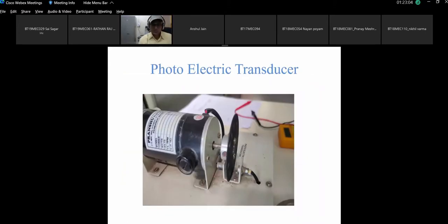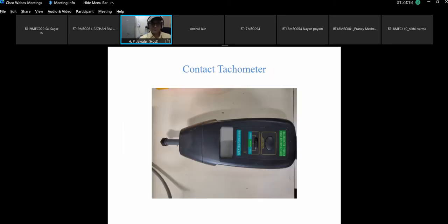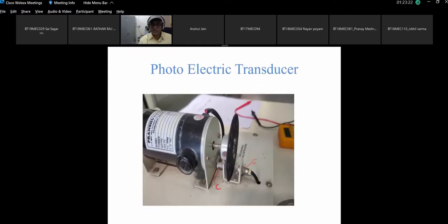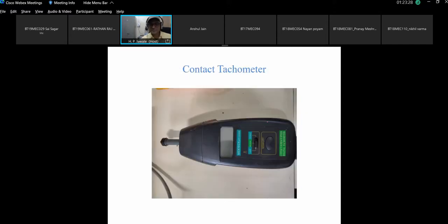So this is a motor. This is the emitter and this is the collector. These are the two elements: light emitting device and light collecting device, or signal collecting device, and this is the disc attached to the motor. This is the tachometer that we are going to use. For measurement of the speed at the shaft, we need to connect the tachometer here. And that tachometer is here. This is the contact type of tachometer that we are going to use.